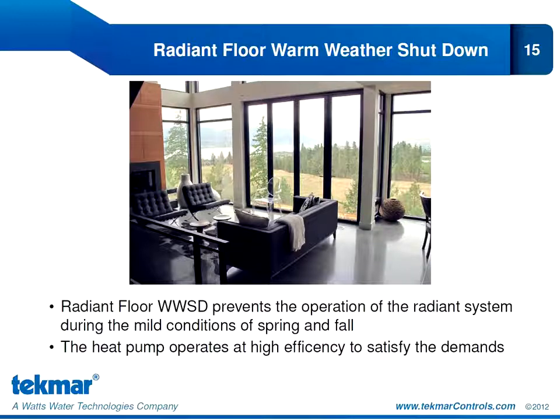What we don't want to do is to charge up our radiant floors in the morning, only to have them continue to radiate heat in the afternoon when we don't need any extra heat. That may force us to turn on our cooling equipment when we otherwise may not have had to. So what this setting does is it allows us to hold off the radiant floor until the temperature is sufficiently cold. And it allows us to use our heat pump instead to answer any of our heating needs.